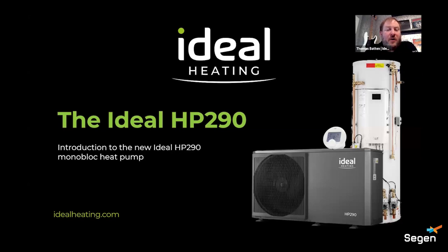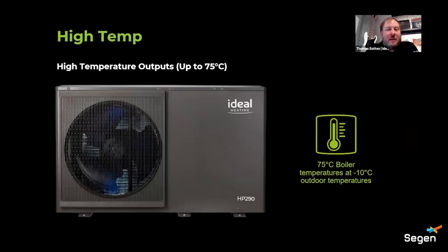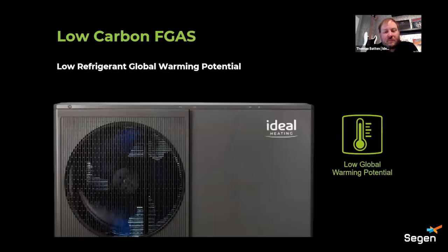HP 290 is our alternative product. So I think where these come in is essentially if you need a slightly higher output, these go up to 14 kilowatts, where the Logicaire tops out at 10. And obviously these are R290, so natural refrigerant. But you still get the same benefits of the Logicaire in terms of it's really easy to install with the control box and the pre-plumbed cylinders. Obviously, with it being a 290 heat pump, it can do higher temperatures. Again, just because it can doesn't mean it should, so I wouldn't necessarily recommend it, but it is capable of doing those higher temperatures. Other benefit of our 290 is obviously the low GWP.